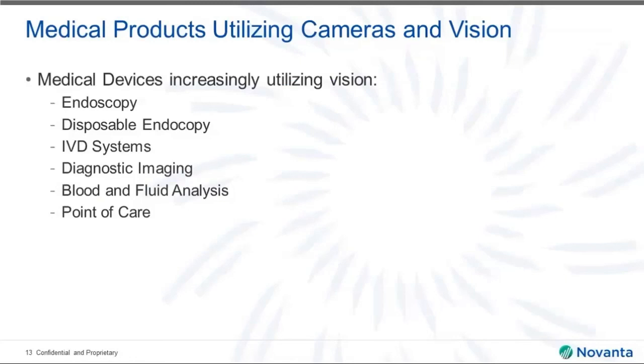In disposable endoscopy, you're starting to see the emergence of tip-mounted image sensors, small diameter sensors, where the image sensor is in a low-cost plastic molded enclosure, and all the image processing is done in a camera control unit. But that endoscope and its image sensor are often a completely disposable, one-use type of application.